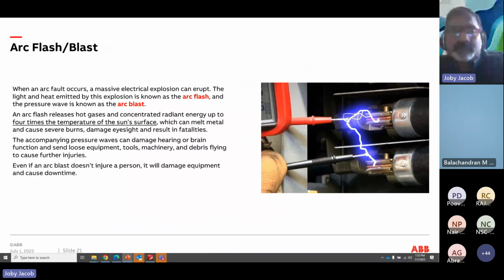Arc flash or arc blast: when an arc flash or fault occurs, a massive electrical explosion can erupt. The heat and light emitted by this explosion is called arc flash, and the pressure wave is known as arc blast. An arc flash normally releases hot gases and concentrated radiant energy up to 4 times the temperature of the sun's surface, which can melt metal, which we already discussed.